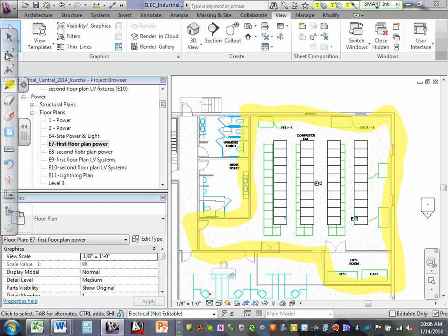So you're gonna put smoke detectors on the ceiling, in the ceiling tile. But you're also gonna put smoke detectors in the subfloor. And let's just call it all 15 foot spacing. So with that said, in the subfloor, one thing that you should know is that you cannot mount the smoke detector upside down. In other words, facing upward. When you look at a smoke detector on the ceiling, let's pretend that that's a smoke detector. That's pointing downward, right?